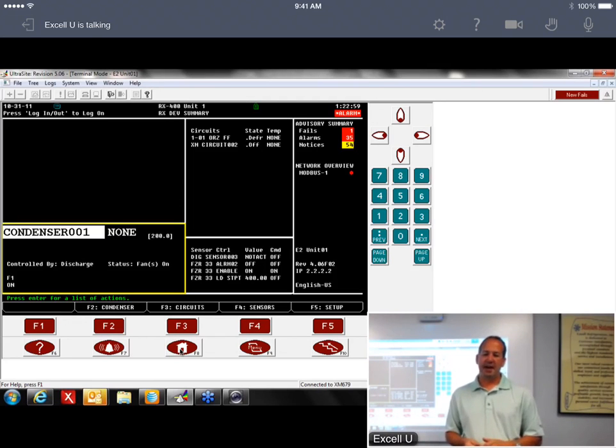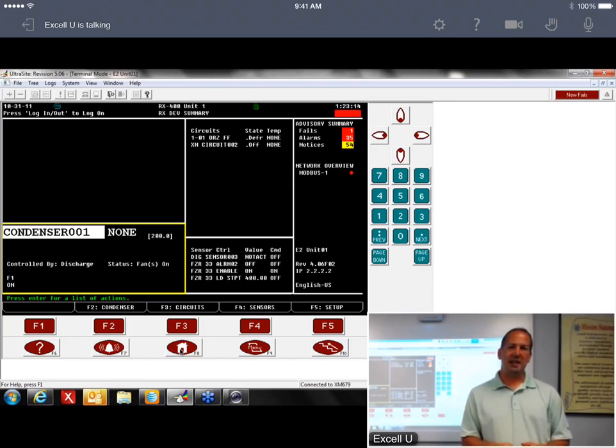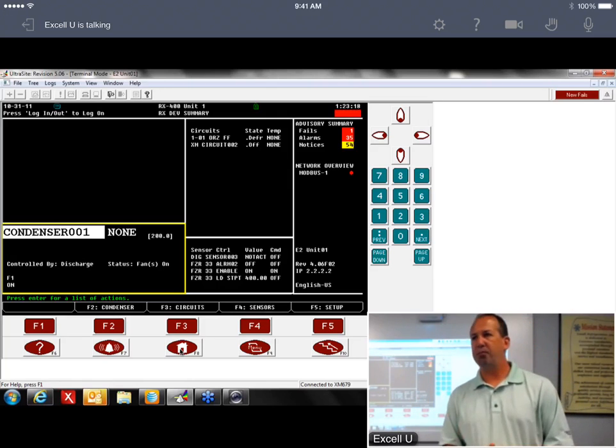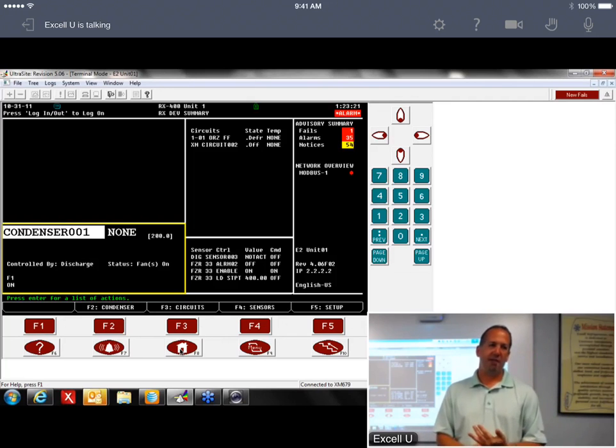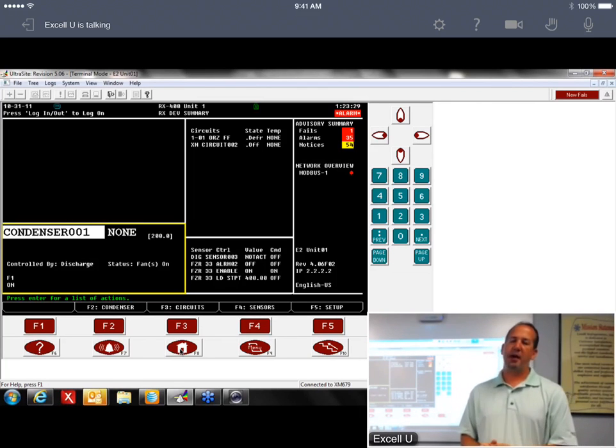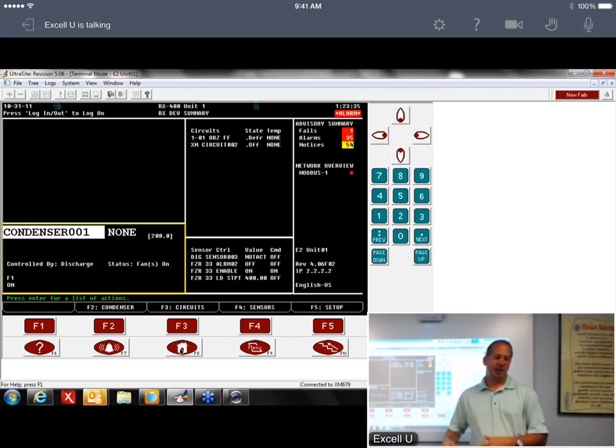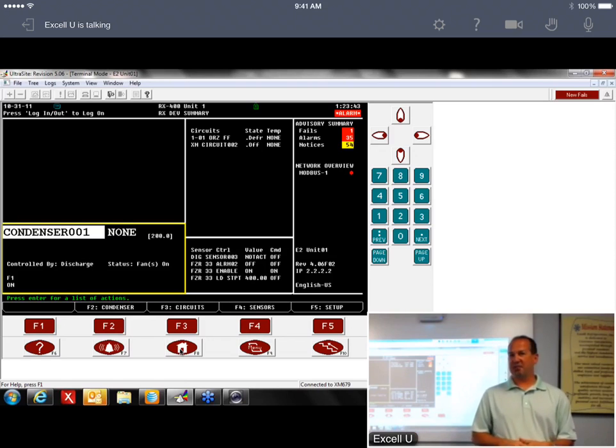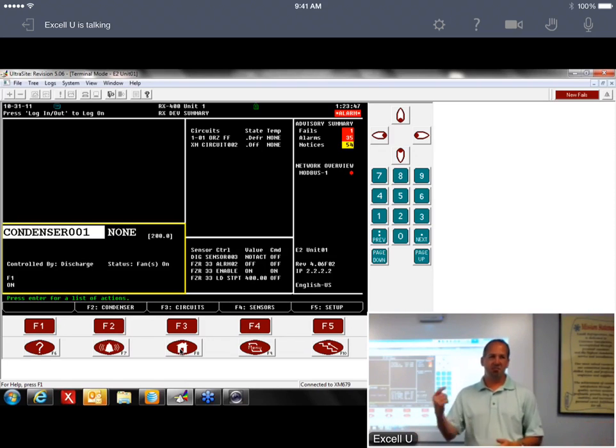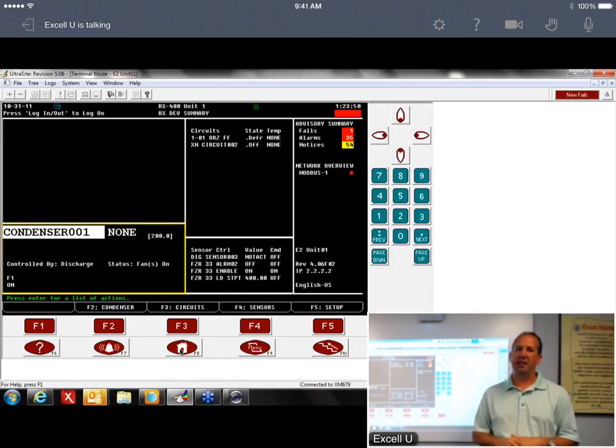So sometimes you may have to reset the device itself, and it'll start to relearn its algorithm. If you get hung up thinking this thing's not working right, sometimes just resetting that device and resetting that algorithm will restart it. Usually if they've done restocking or something like that, that short of a time frame won't screw it up if it's been running pretty good for a while. But if you first turn the thing on and they're loading it up and it can't make temperature for a couple hours, what I'd do is reset the device the next day or so when things have settled out, because you don't want those trends in the algorithm.